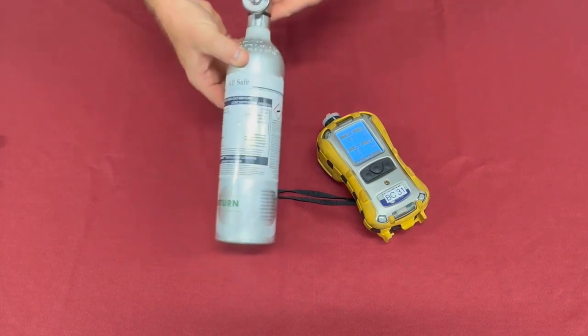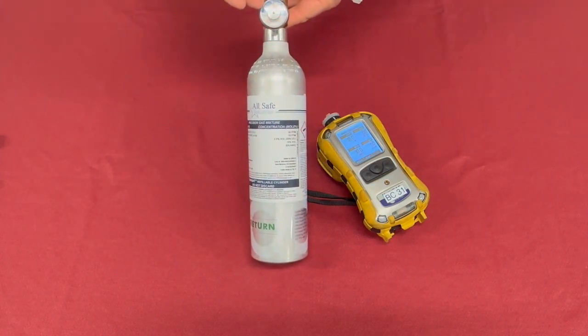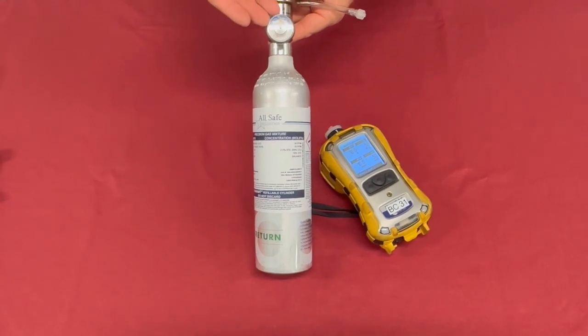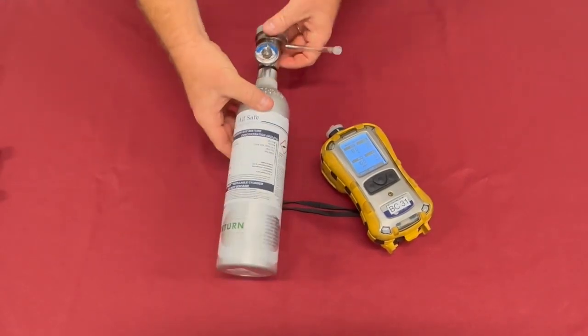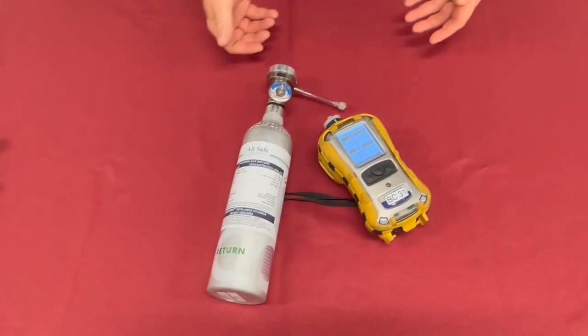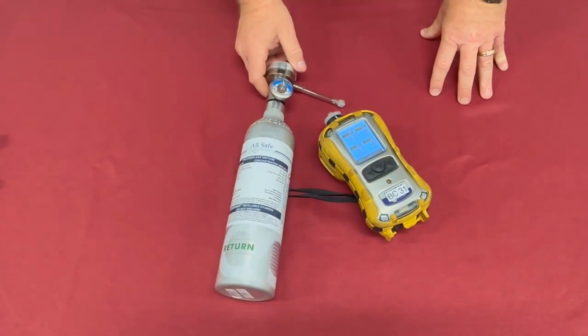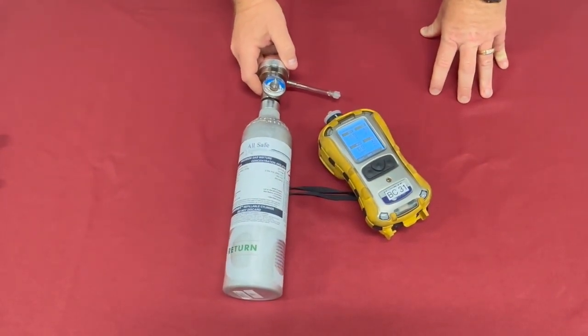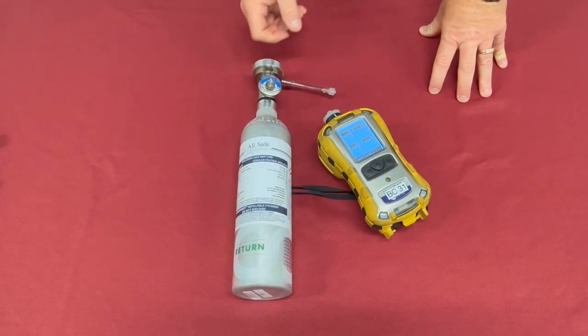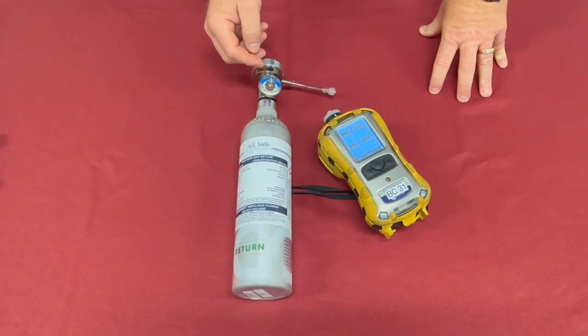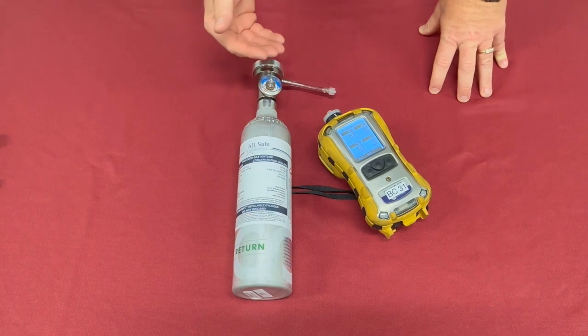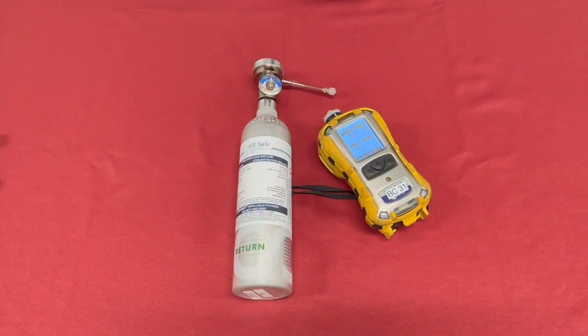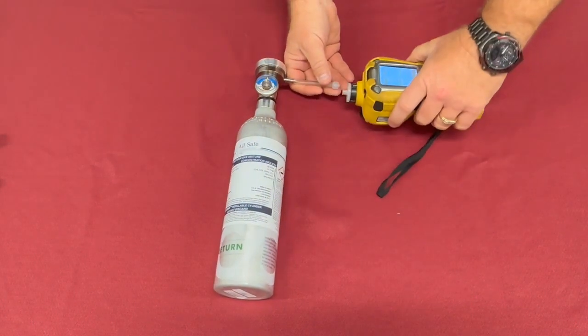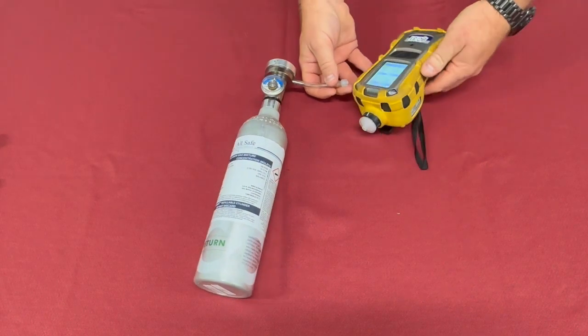When you go to hook this up, first of all, before you get started, make sure you have calibration gas in your cylinder. If you don't have calibration gas, it will fail the test. Now we want to use these cylinders down to empty. They're very expensive, so even if the cylinder's showing almost empty, go ahead and try to do a calibration. If it fails during the middle of it, that's okay. We can get you more calibration gas. But they actually go pretty far, even when they look like they're empty.